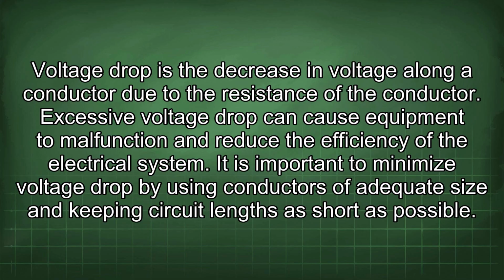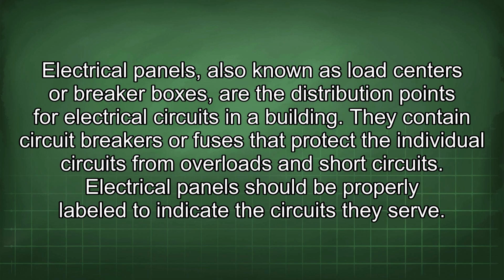Excessive voltage drop can cause equipment to malfunction and reduce the efficiency of the electrical system. It is important to minimize voltage drop by using conductors of adequate size and keeping circuit lengths as short as possible. Electrical panels, also known as load centers or breaker boxes, are the distribution points for electrical circuits in a building. They contain circuit breakers or fuses that protect the individual circuits from overloads and short circuits. Electrical panels should be properly labeled to indicate the circuits they serve.